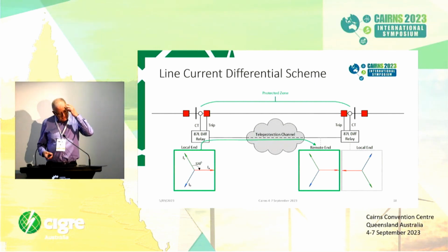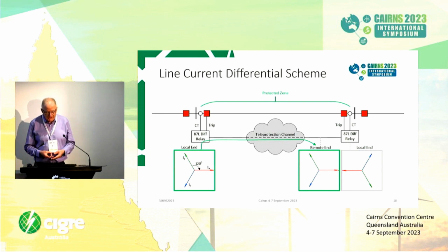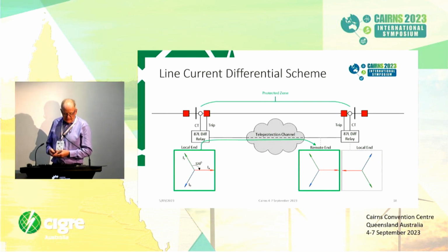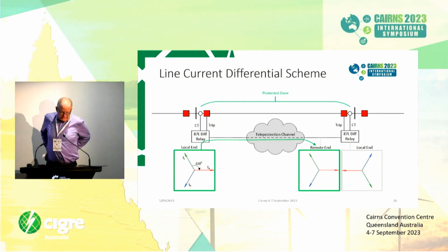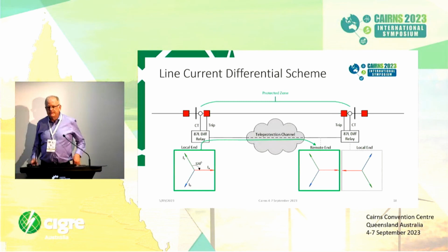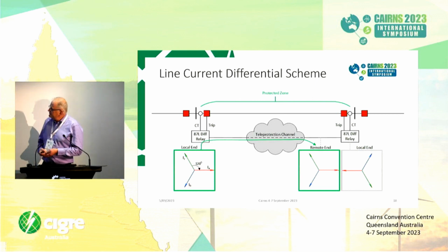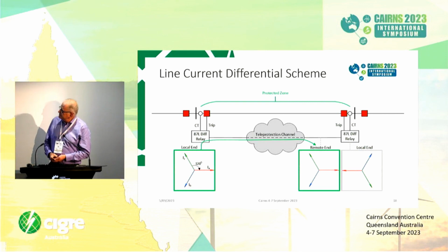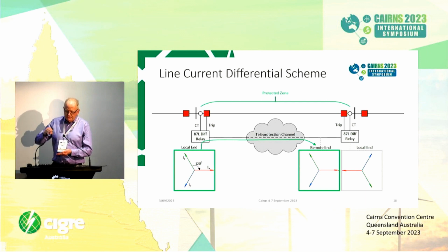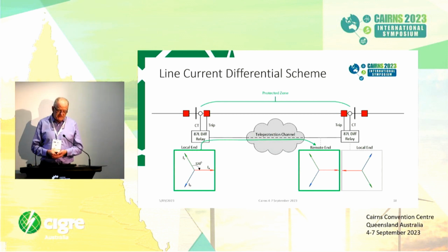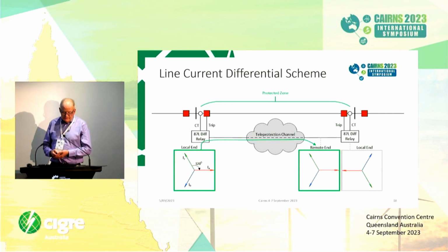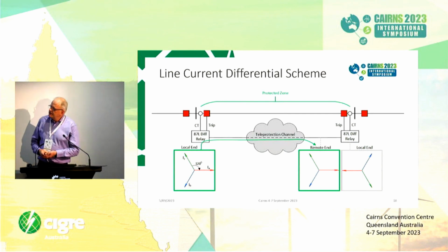This scheme sends analogue signals from the local end of the transmission line to the remote end via a telecommunication channel. Importantly, the way this scheme works, it's basically sending current waveforms or current vectors from one end to the other. Vectors include the magnitude of the currents, which is the digital data that gets transmitted across your network. But it also includes the phase angle of the current vector, which is basically time information.